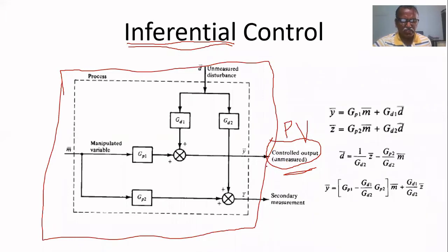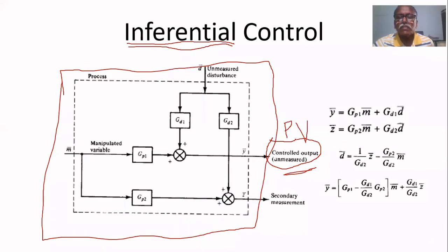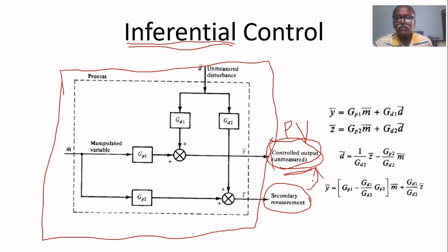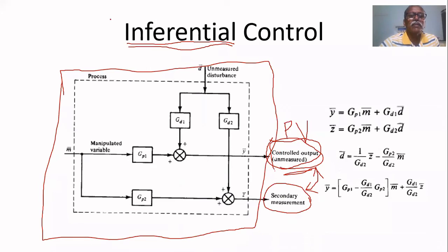Similarly, in this process, it is not possible to measure the process variable directly. But we can measure another variable, called the secondary measurement, which has a good relationship with the process variable and can be measured. In that case, we measure this secondary variable and control the process — that is called inferential control.